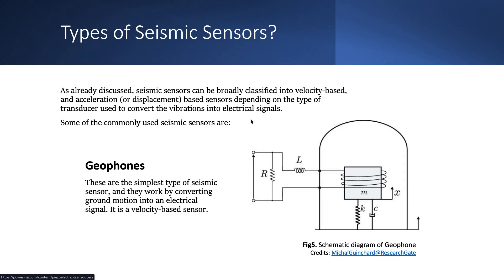There are various types of seismic sensors that are based on accelerometers or velometers. First of all, we may talk of geophones. It's also called a seismometer, a velocity based meter. This is a spring, the mass attached to it, and this is a damping medium. Whenever there is vibration in a surface or whatever surface it is placed on, the mass attains some velocity, and due to this velocity, there is a voltage that is generated at these two terminals. What this damping medium does is it seizes the motion as early as possible.